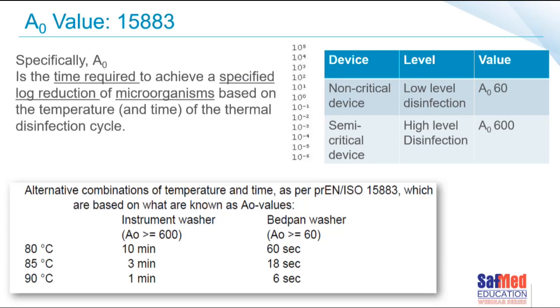ISO and SANS 15883 describe the concept known as the A0 value — the time required to achieve a specified log reduction of microorganisms based on the temperature and time of the thermal disinfection cycle. In steam sterilization we want a log reduction to 10⁻⁶; with disinfection it is not as high, but we still need to clearly disinfect our instruments. A manufacturer can, for example, set the water temperature at 90°C to achieve the correct level of disinfection. At 90°C, the standard states that the disinfection cycle in an instrument washer must run for a minimum of one minute.